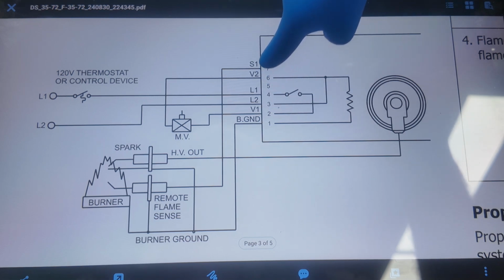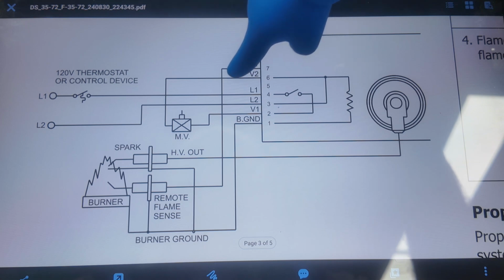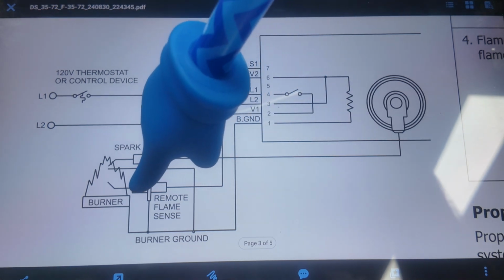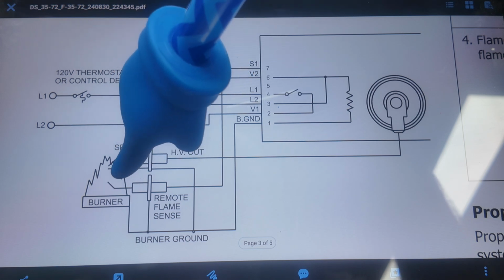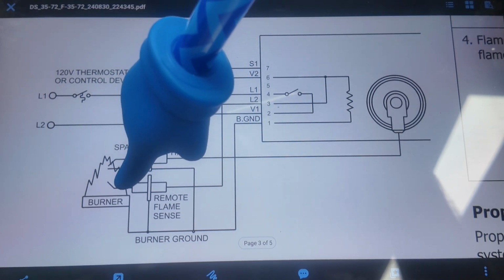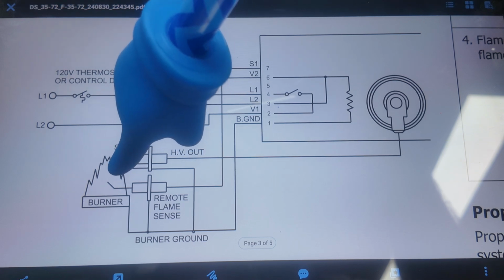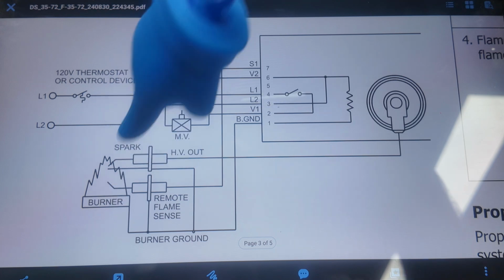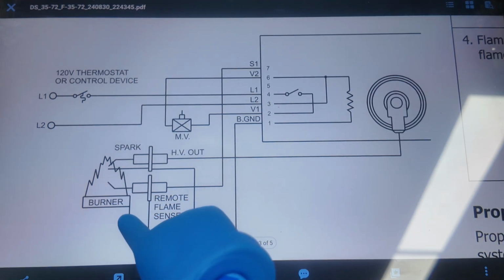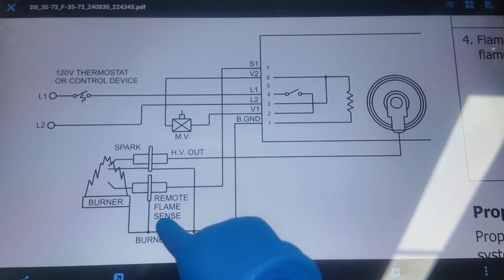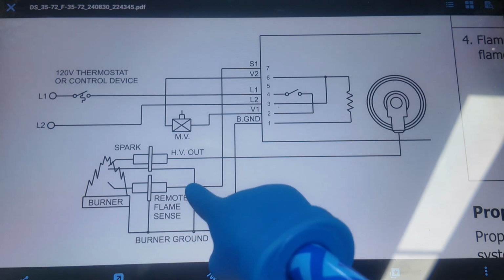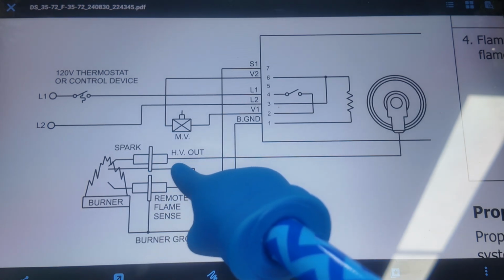So we have S1. S1 is the flame sensor. That goes down here and goes to the sensor that is in the flame to monitor the flame. It puts voltage into that rod, wire and rod, and draws milliamps through the flame to ground. Now the burner is connected to burner ground.